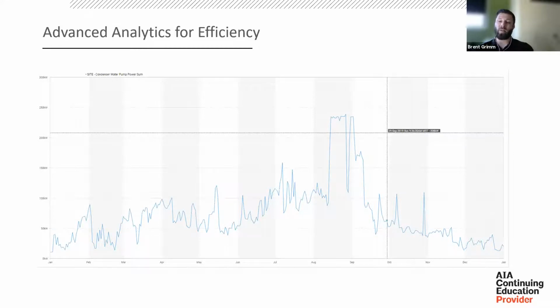These are the types of events that we notice really just get lost in the background noise of a facility. It's not likely that an operator is just going to pull up condenser water pumps and see how much power they're using, as long as that condenser water temperature is being met. So there's a good chance that this would have gone on for months without a proper monitoring-based commissioning program in place. Now, the only downside of this event, it was a learning experience for us.